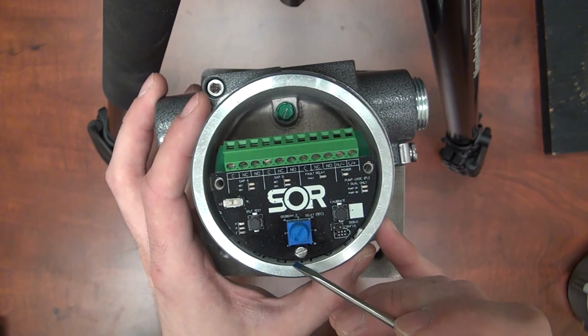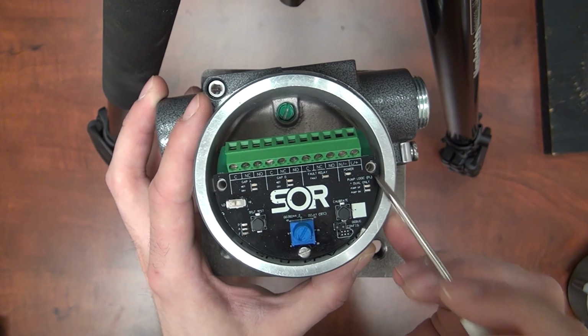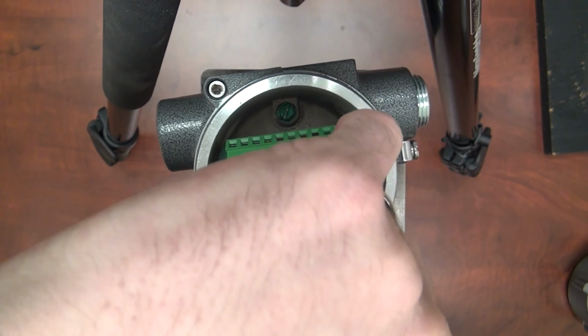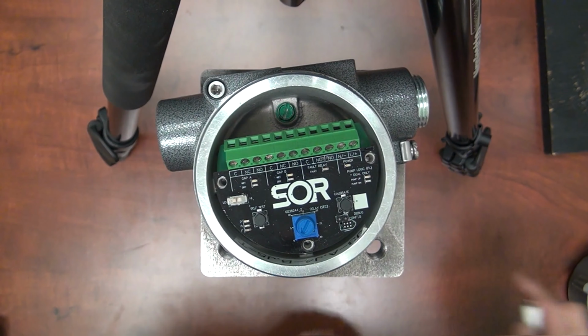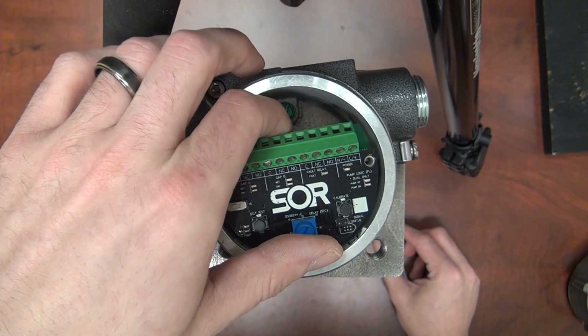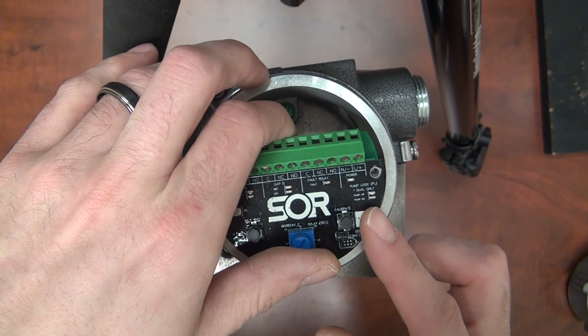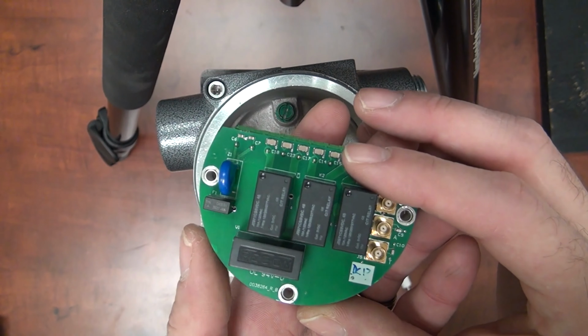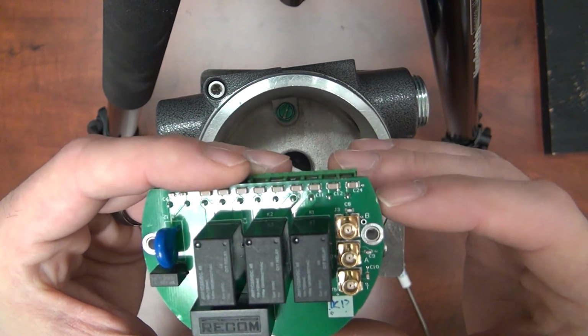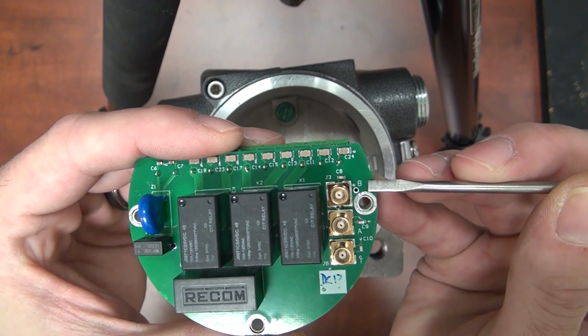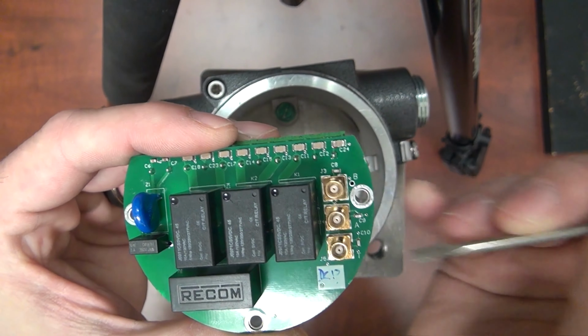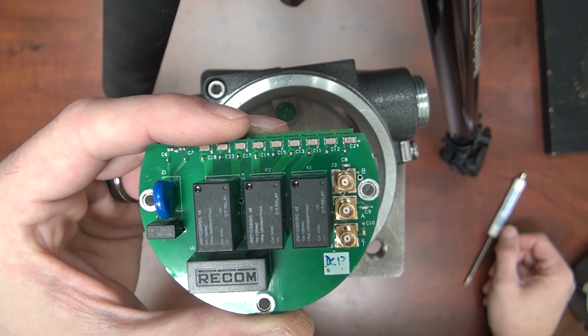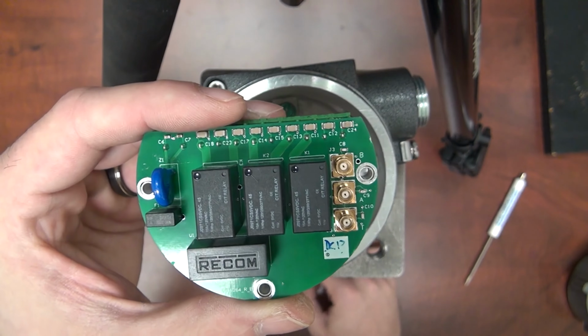To start, remove the housing cover. Start by removing the screws located here, here, and here on the interface board. After the screws have been removed, the interface board can be removed. It is an assembly of two boards with the interface board on top and the power board below. On the power board are three connection points labeled B, A, and T. These three connectors are where the probe cable connections will connect to.